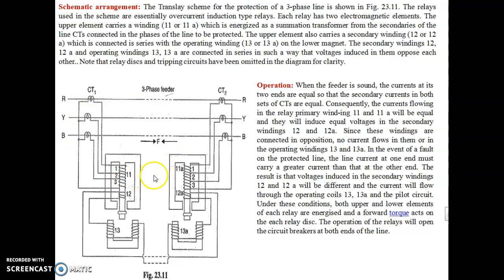Okay, so here the upper magnet of the relay carries the summation winding. This is the upper magnet, that is M shaped. It carries the summation winding to receive the output of the current transformer, that is, the summed value. It comes to the M shaped upper magnet, which receives it. Okay, it circulates through the pilot wires and hence through the lower magnet of the disc. Okay, this is the schematic arrangement of the Translay relay.